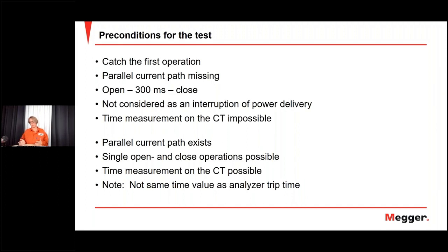But if you have a parallel path, you can make a real slow, normal open and short after do a close again, but then you have an interruption in that specific bay, right? And then you can measure also the time measurement in the CTs. So you're going to measure whether there is an AC or not. But you will get opening time, not trip time. So you have to be aware of that when you compare the results after an analysis.